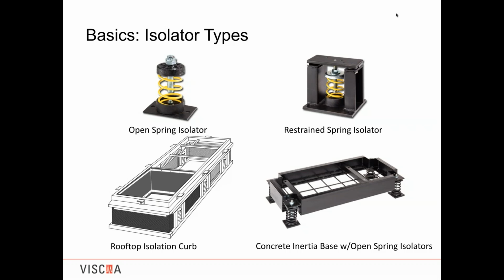Now, I might have passed over this, so I'm going to go back for a slight thought on the spring isolators. When we talk about deflection, I don't want to confuse people with this. A 4-inch deflection spring that deflects 4 inches statically does not move up and down 4 inches during operation. I've had some people ask that question, and it may sound a little ludicrous to someone in the industry, but when you're not familiar with it, it's a good question. In general, after the static deflection is put in, whether it's 1/4 of an inch or 4 inches, as the equipment is operating and moving, the spring or whatever vibration isolator is in between would move very little. We're talking on the order of magnitude of 1/16 of an inch, you'll see it oscillate up and down.